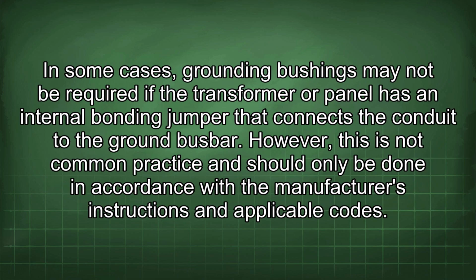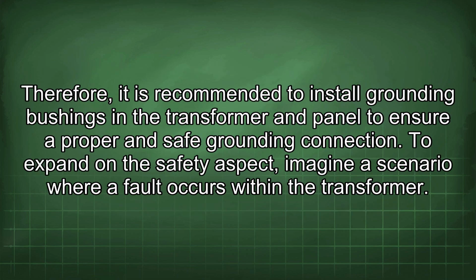In some cases, grounding bushings may not be required if the transformer or panel has an internal bonding jumper that connects the conduit to the ground busbar. However, this is not common practice and should only be done in accordance with the manufacturer's instructions and applicable codes.